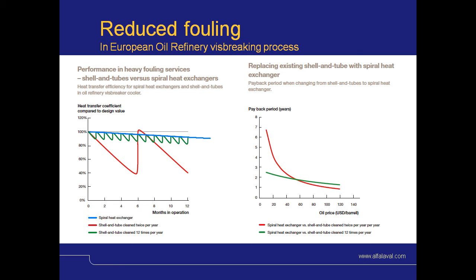These graphs show the performance of fouling heat exchangers. It shows shell and tubes versus spiral heat exchangers. The graph to the left, the red line, shows a shell and tube heat exchanger which is cleaned once every 6 months. So the efficiency goes steadily down until it's cleaned, when it's up to 100% again. The green graph shows a shell and tube heat exchanger that is cleaned every month, and the blue line shows a spiral heat exchanger with its self-cleaning effect. The graph to the right shows the payback period when replacing existing shell and tube with spiral heat exchanger. The red line corresponds to the red line to the left, and the green line corresponds to the green line to the left.